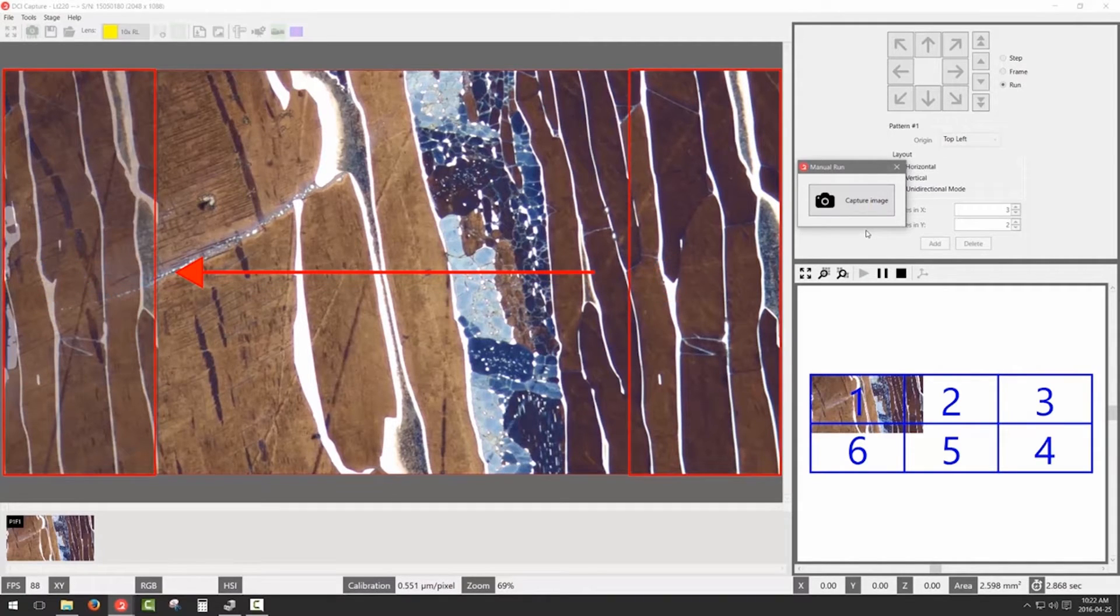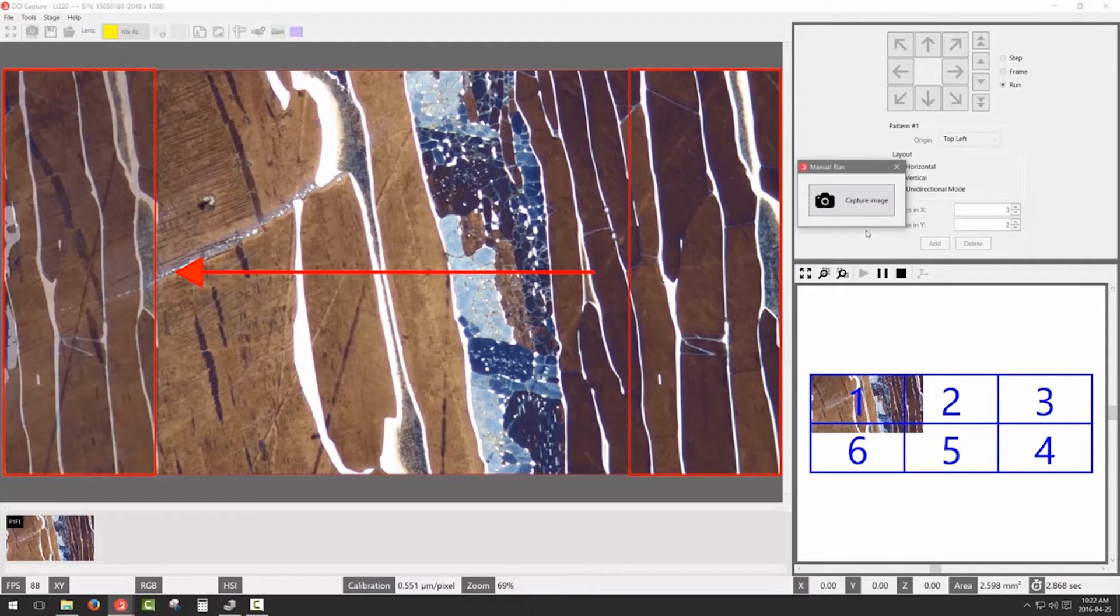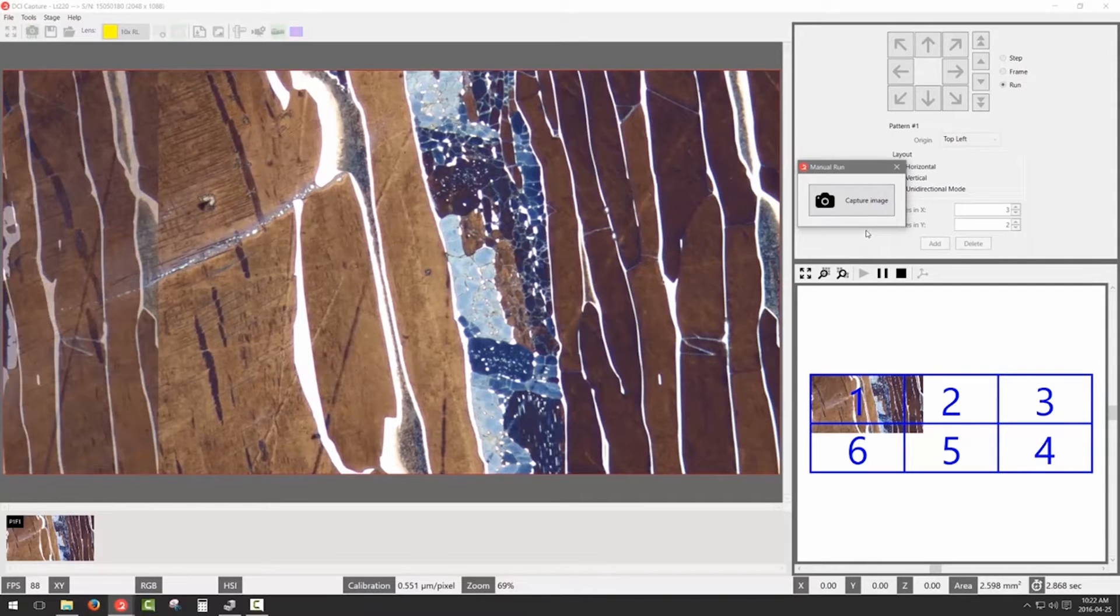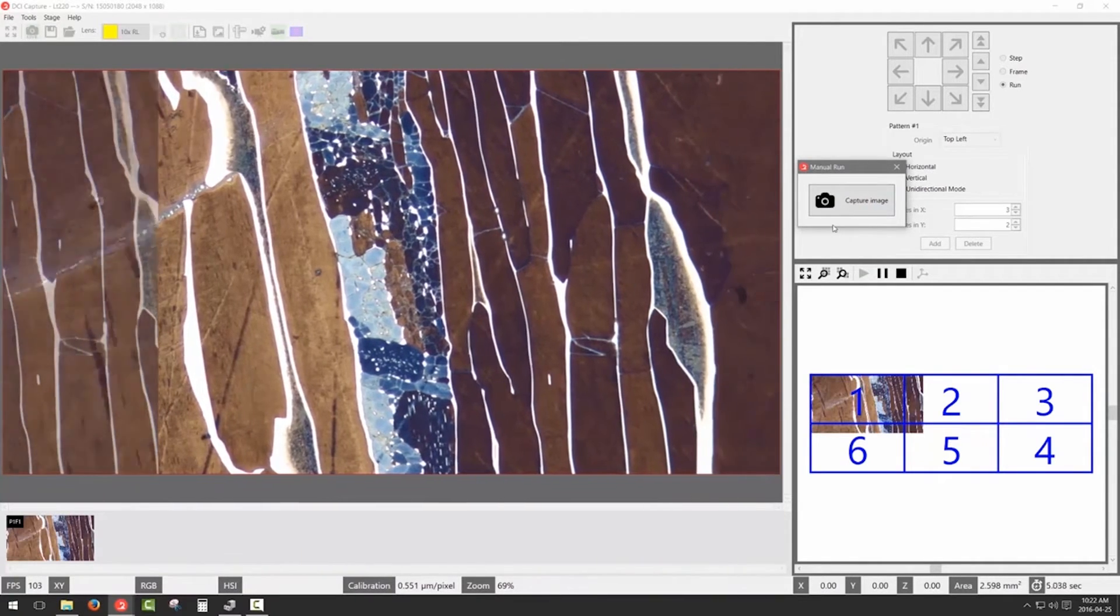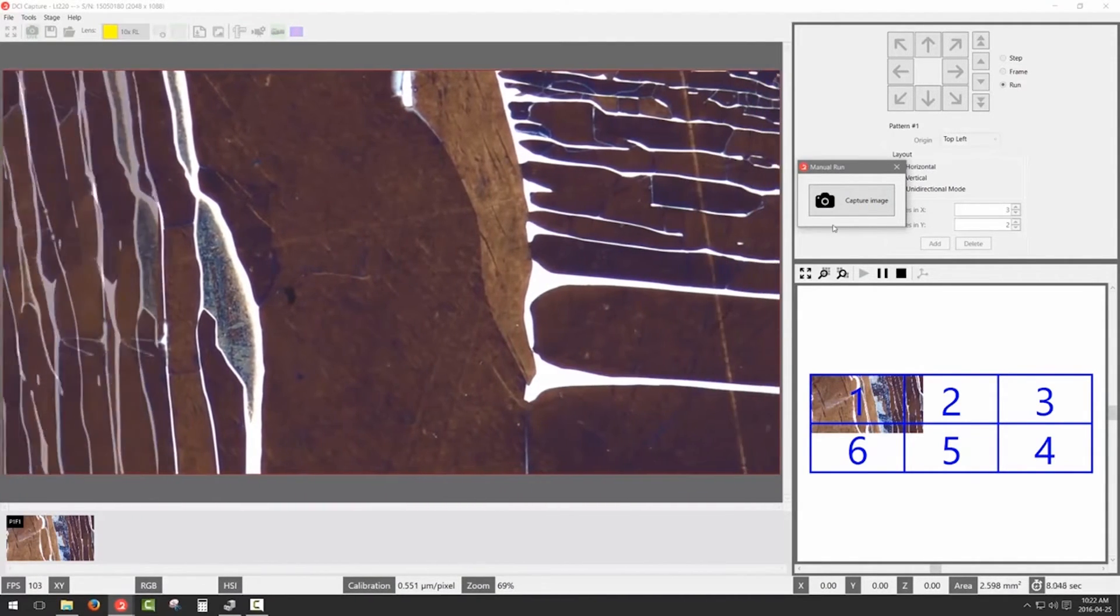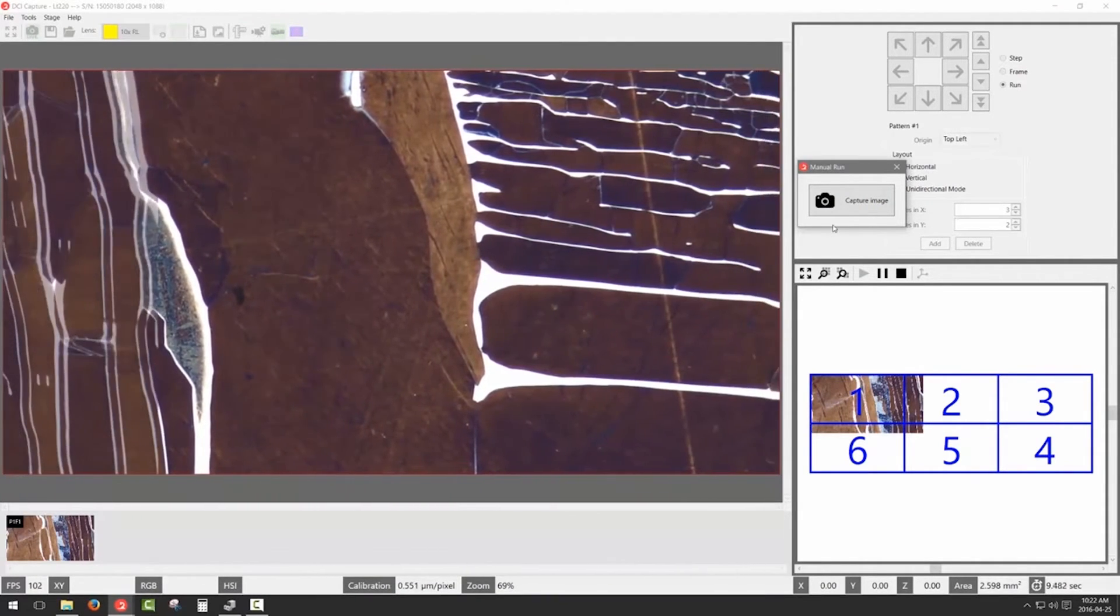Start moving the sample right to left, slowly, to bring the section on the right side of the image window under the overlay. Once it is done, click the capture button or hit the space bar. Repeat for each field.